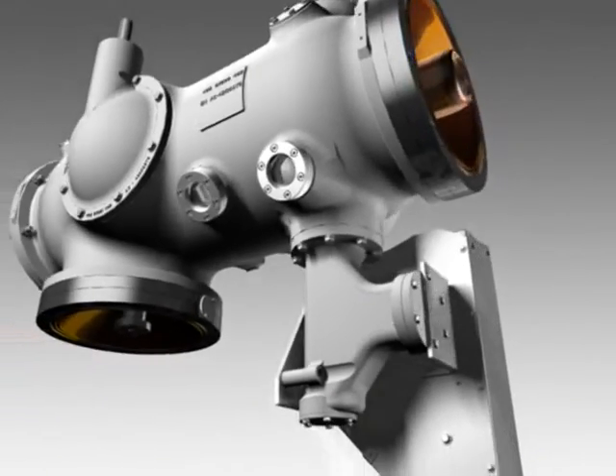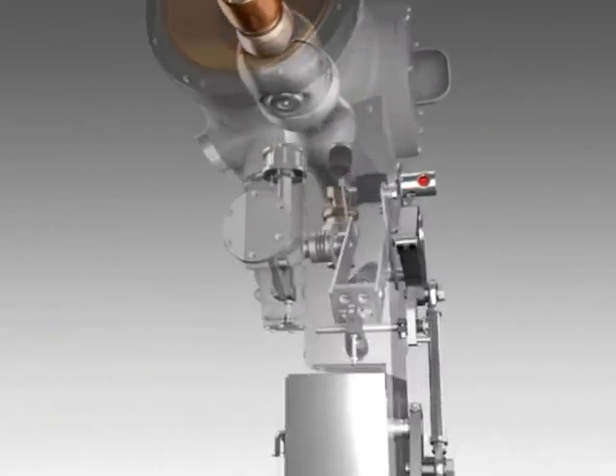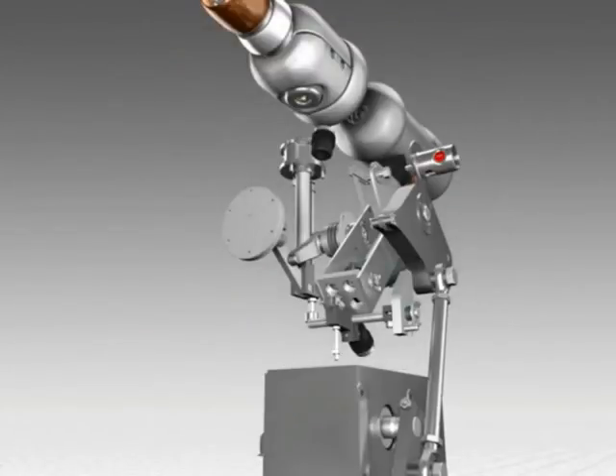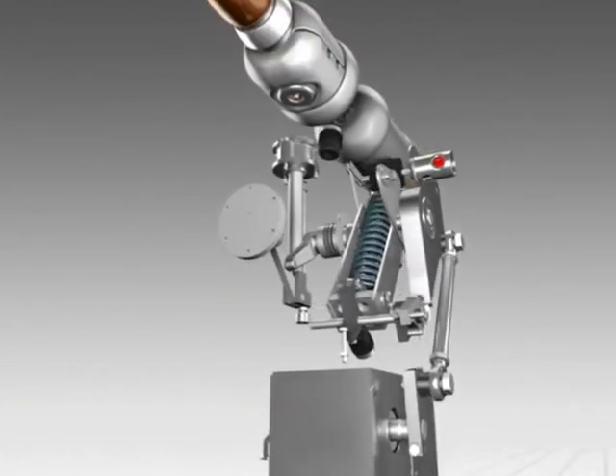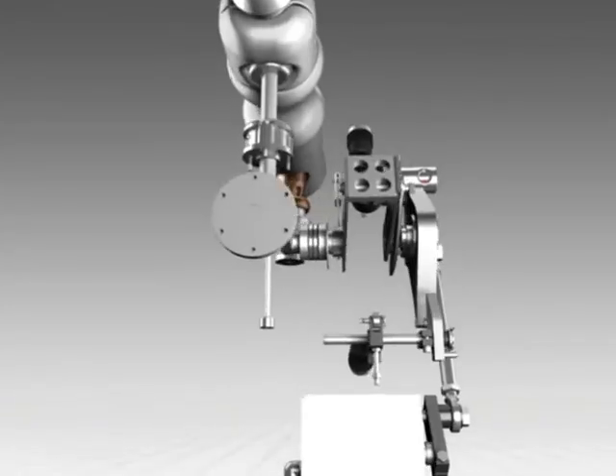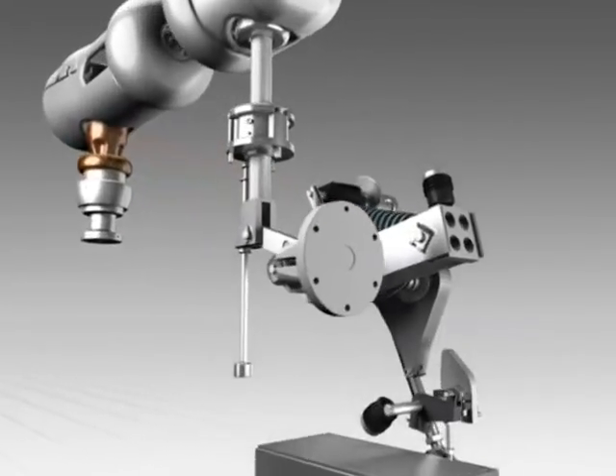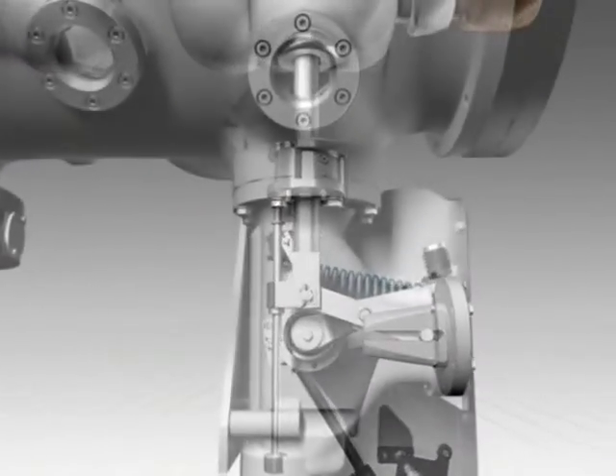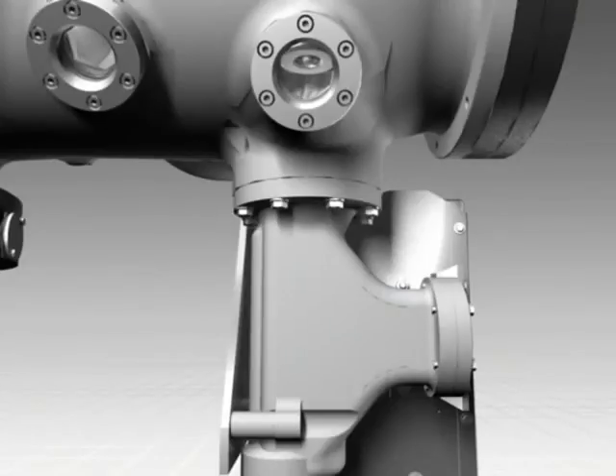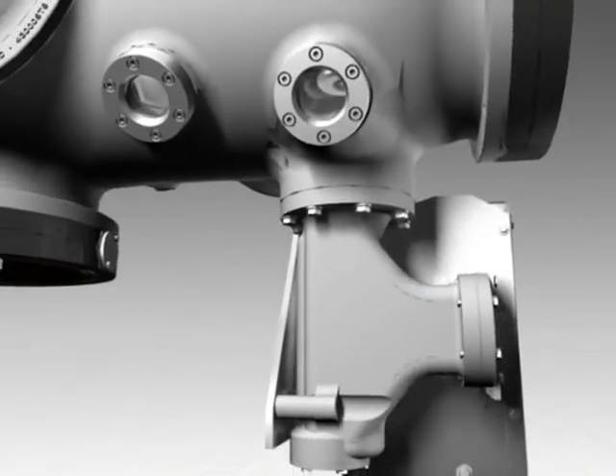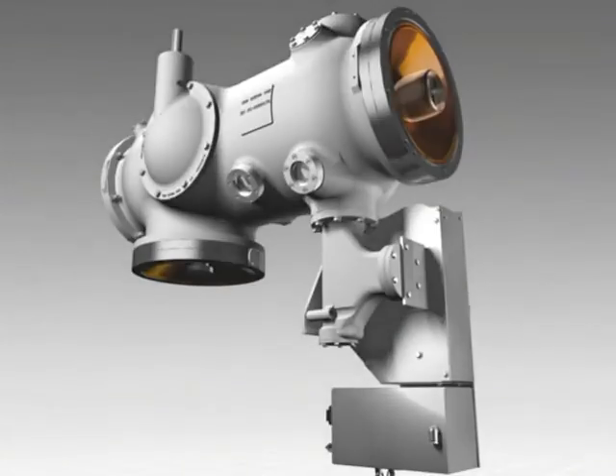The high-speed earthing switch is make-proof. It achieves high-speed action by a spring-operated mechanism charged by an electric motor. A so-called pin-type design contact system ensures that the conducting path is reliably earthed, even if it is inadvertently switched into connection with live equipment.